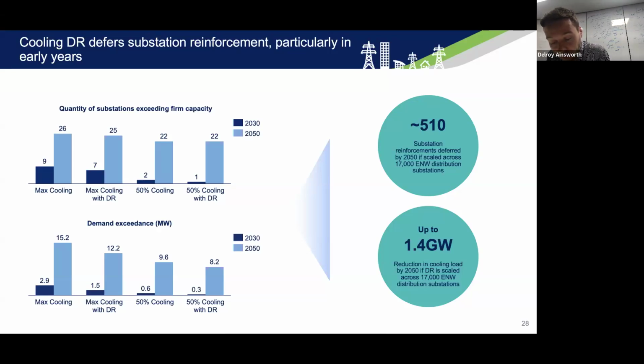The 4 scenarios shown on the graphs are max cooling, which assumes all overheated buildings install AC, max cooling with DR, which assumes all overheated buildings install AC and customers participate in a DR program, 50% cooling, which assumes 50% of overheated buildings install AC, and 50% cooling with DR, which assumes 50% of overheated buildings install AC and customers participate in a DR program. So looking at the top graph, max cooling uptake shows that 9 of the 36 substations exceeded capacity by 2030 and 26 of the 36 by 2050. Using DR, deferred reinforcement on 2 substations by 2030 and 1 by 2050. For the 50% cooling uptake, 2 of the 36 substations exceeded capacity by 2030 and 22 of 36 by 2050. Using DR, deferred reinforcement on 1 substation by 2030 and 0 by 2050.